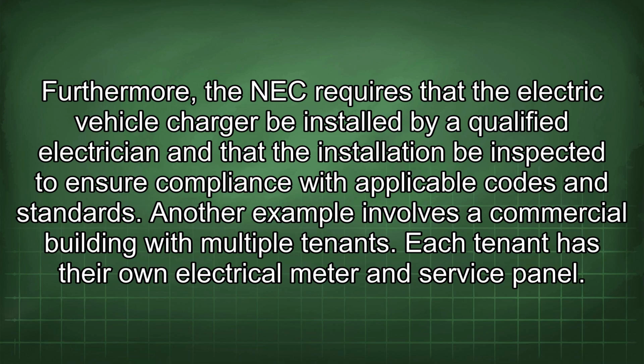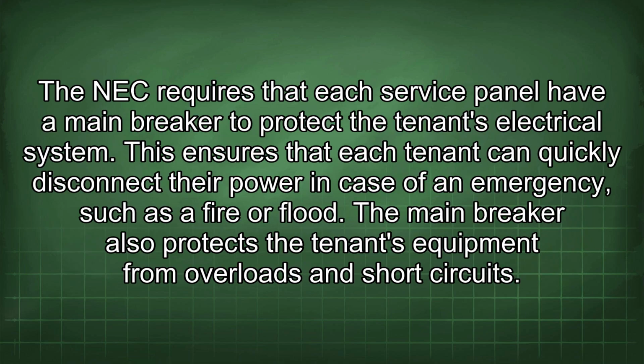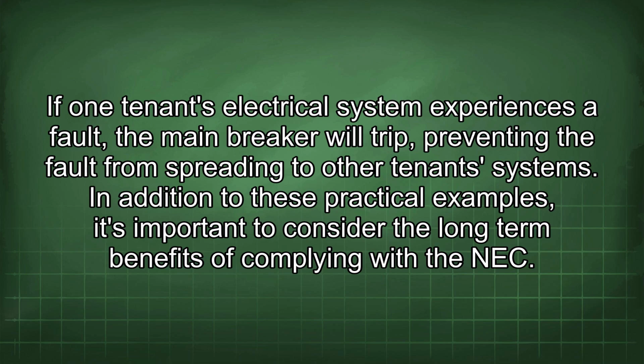Another example involves a commercial building with multiple tenants. Each tenant has their own electrical meter and service panel. The NEC requires that each service panel have a main breaker to protect the tenant's electrical system. This ensures that each tenant can quickly disconnect their power in case of an emergency, such as a fire or flood. The main breaker also protects the tenant's equipment from overloads and short circuits. If one tenant's electrical system experiences a fault, the main breaker will trip, preventing the fault from spreading to other tenant systems.